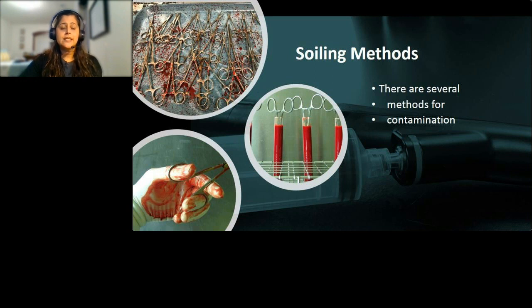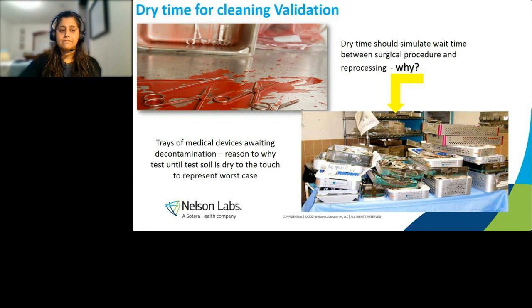There are several different methods of soiling. We have immersion. If it's going directly into the body cavity, we would immerse the device directly into the blood soil, just like we have the hemostats here. If it's a spray, we would take a spray bottle and spray the devices. The spray would simulate if you're cutting something in the body and it just sprays out. Then there's handling with soiled gloves, which is a common practice that we do all the time. And in the hidden background, you see here, we have flushing of the channels in the endoscope. Any lumens on the device will be flushed with the test soil to challenge the lumen cleanability.